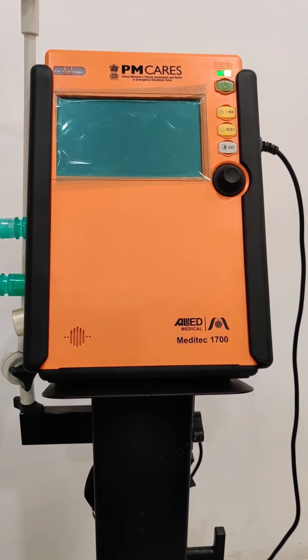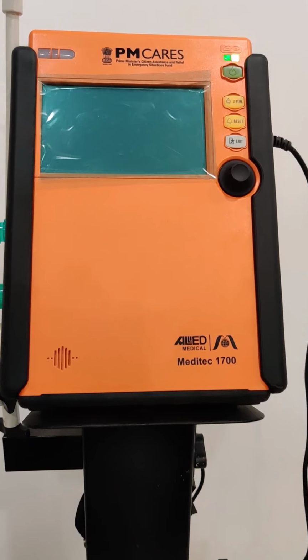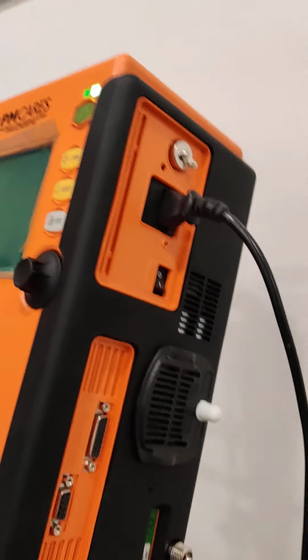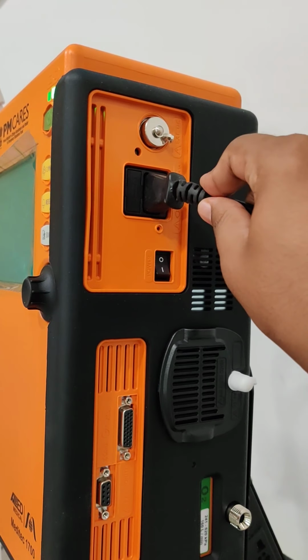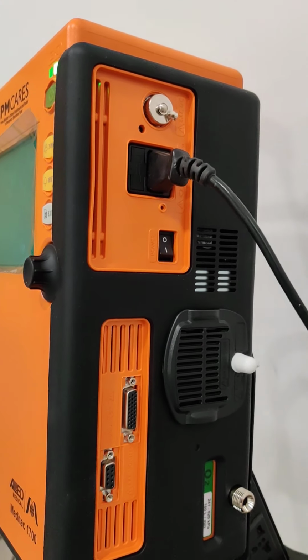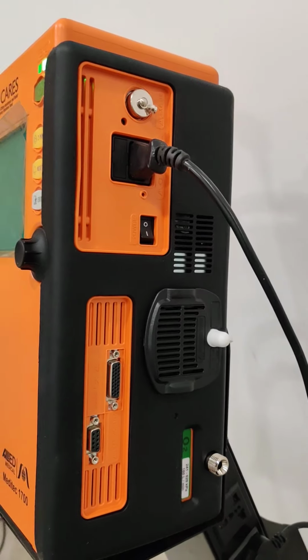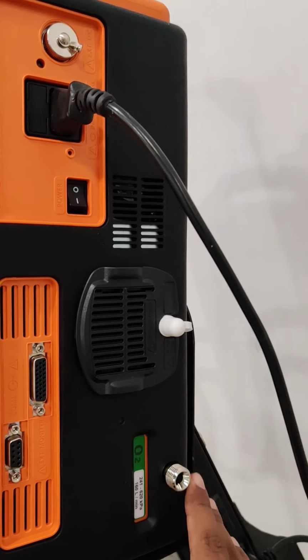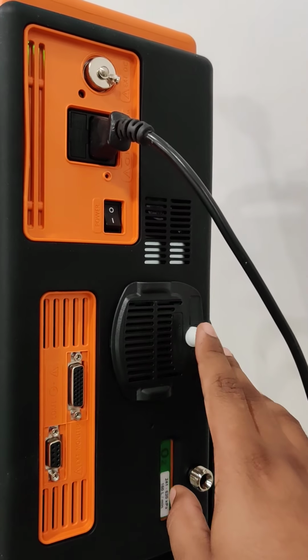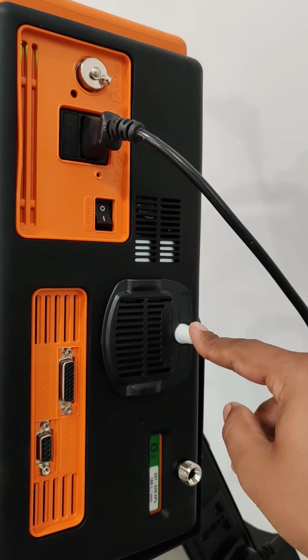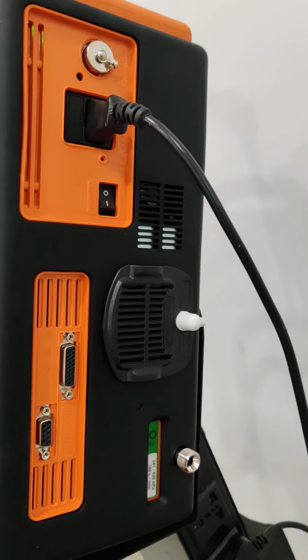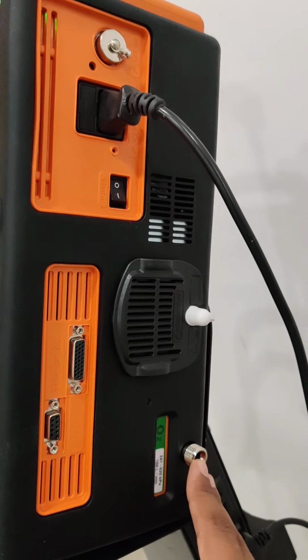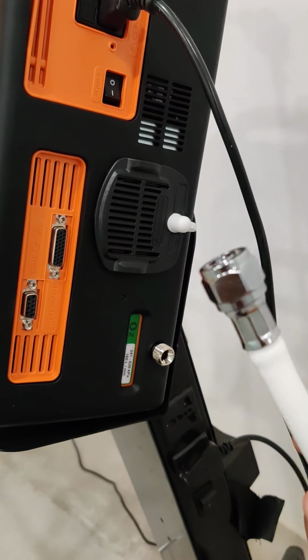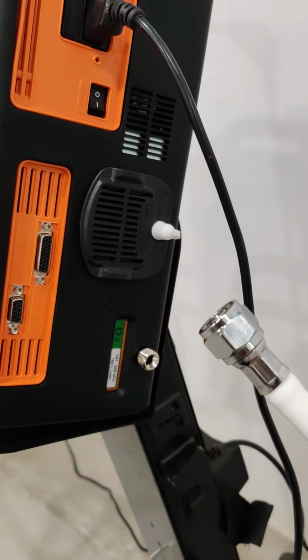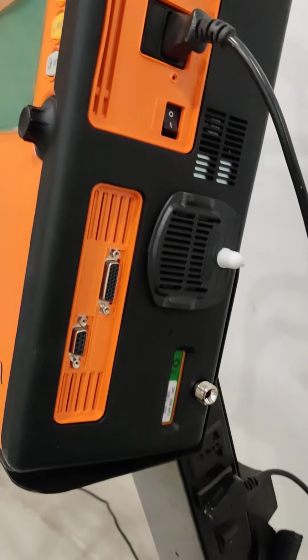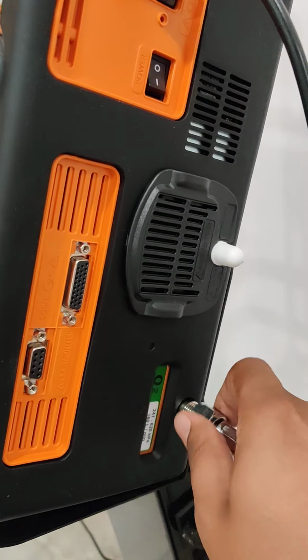So now I am going to discuss the various connections of the ventilator. On the right hand side, this is the mains power connection. Here you can connect the mains power, and for oxygen enrichment we are giving two options. One is you can connect the high pressure, and this you can connect with the auxiliary flow meters or the oxygen concentrator. For high pressure connections, this is the tubing for high pressure connection which we supply as a standard supply with the machine. So here you can connect it like this.